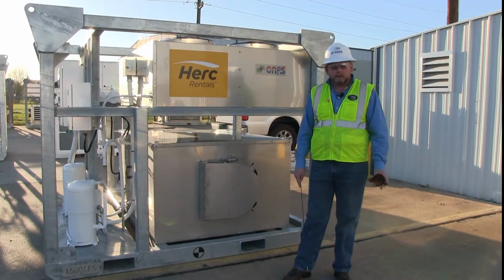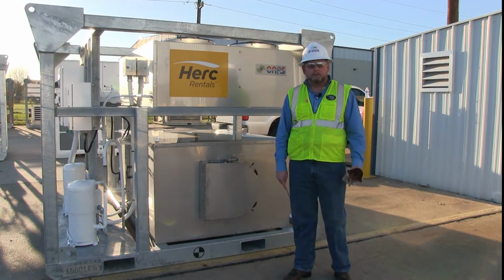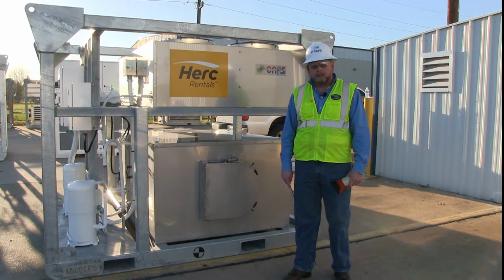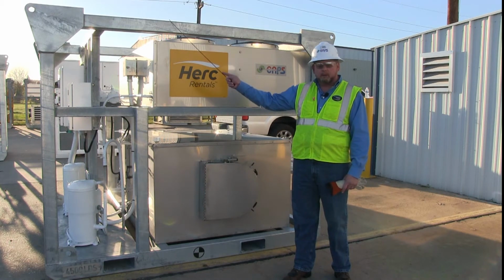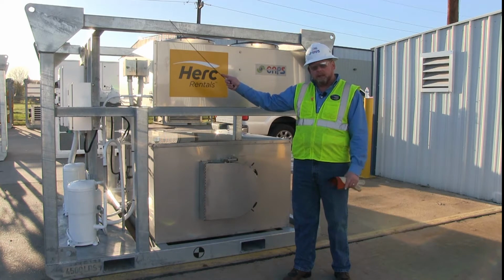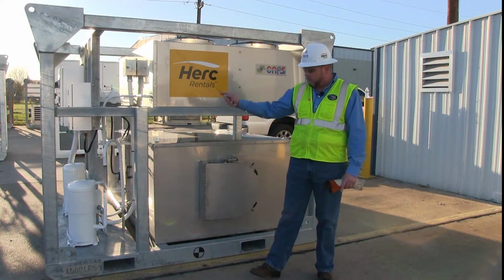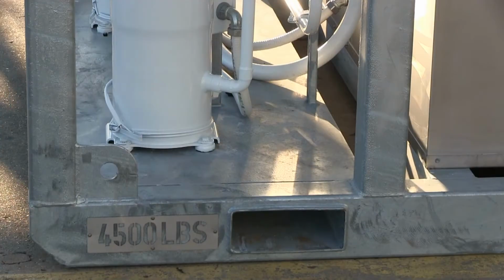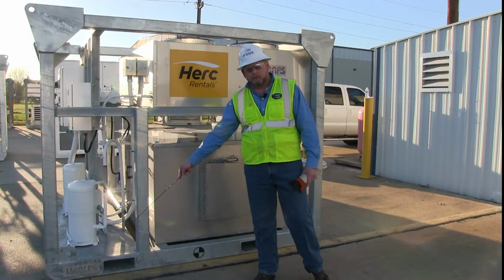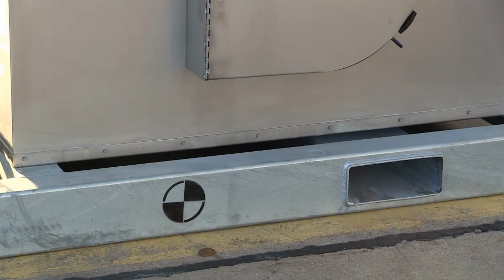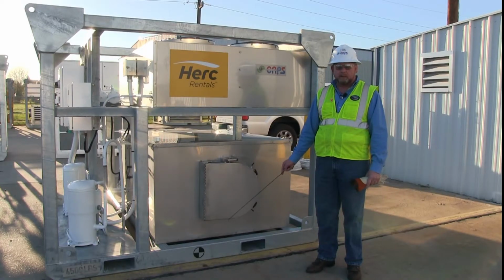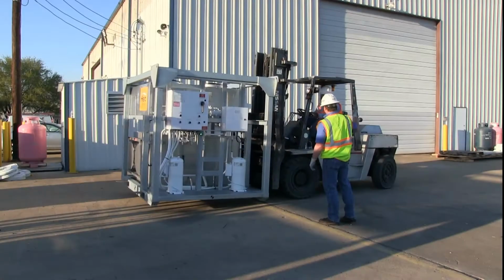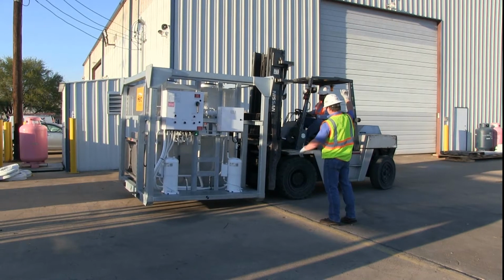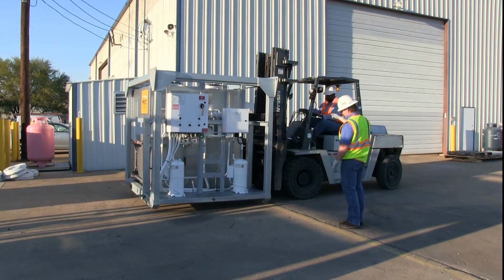The 20-ton industrial unit is designed to be moved by two methods. The first one is the forklift truck, or second, we have designed overhead single point lifting. First thing that needs to be checked before moving the unit is the weight tag in the lower corner to ensure that the forklift is sized properly for moving the machine. The center of gravity is clearly marked on all of our units for overhead lifting and transporting. As the unit is being positioned into place, please ensure that the machine is set on a stable and level ground.